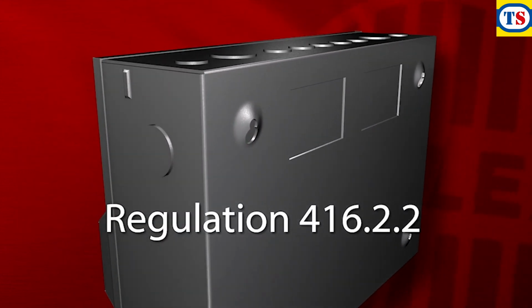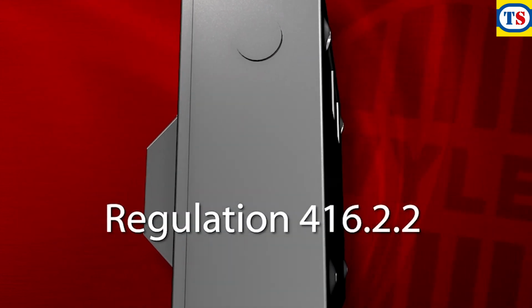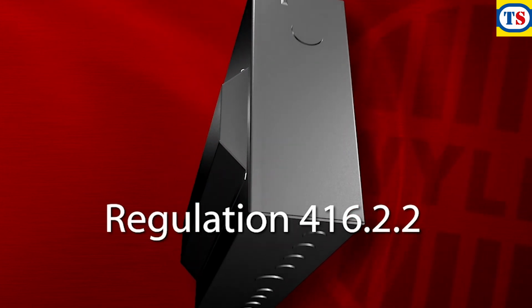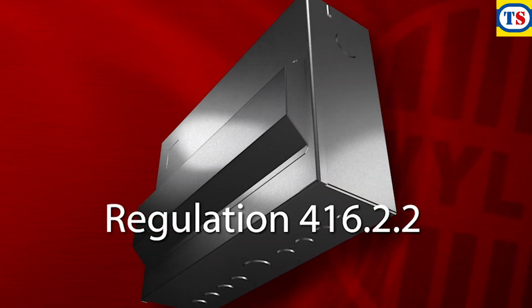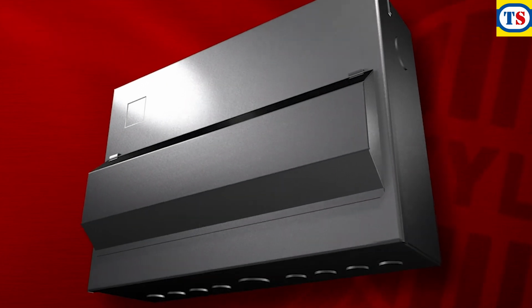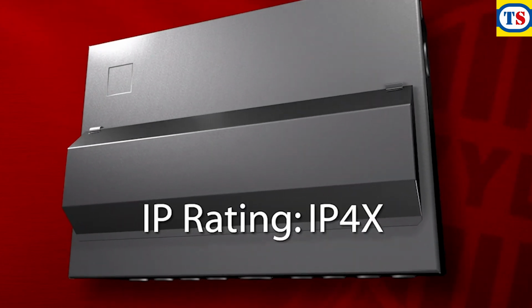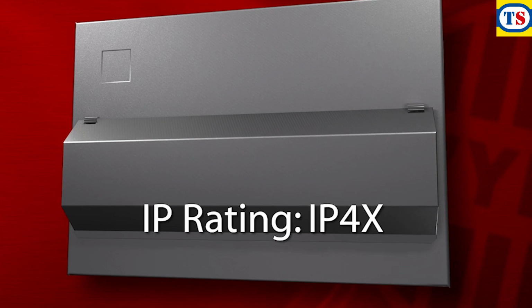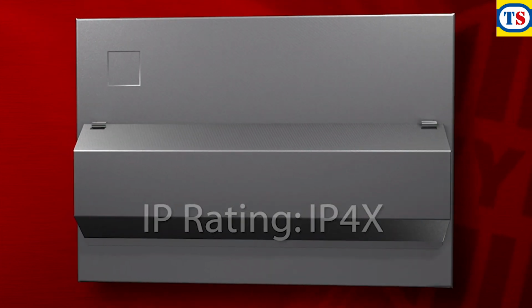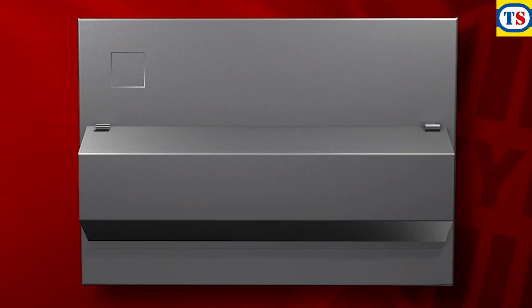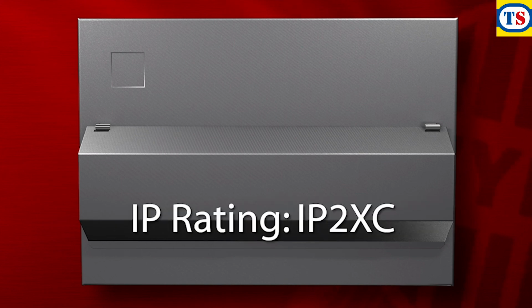Regulation 416.2.2 of the wiring regulations also requires the installer to ensure that the consumer unit, when fully installed, achieves an IP rating of IP4X on the top elevation if this is readily accessible, and elsewhere on the consumer unit the other elevations of the enclosure must be to IP2XC.